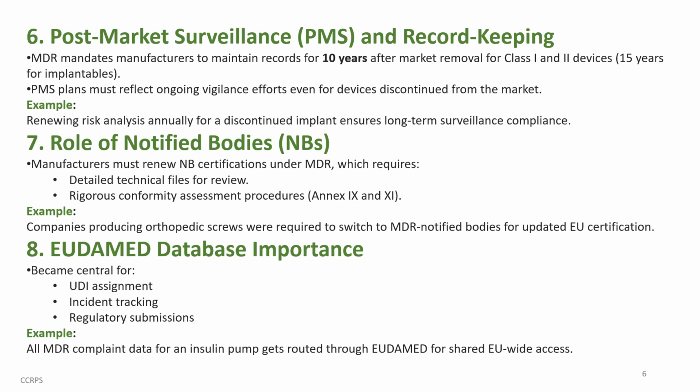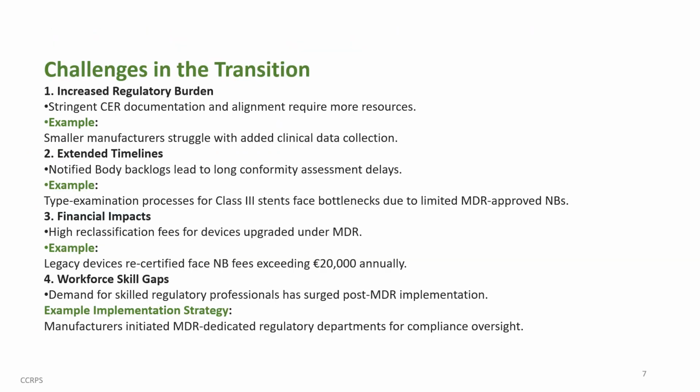Role of NBs, or notified bodies. Manufacturers must renew NB certifications under MDR, which requires detailed technical files for review. Rigorous conformity assessment procedures, Annexes 9 and 11. Example: companies producing orthopedic screws were required to switch to MDR notified bodies for updated European Union certifications. EUDAMED data's importance: it became central for UDI assignment, incident tracking, and regulatory submissions. Example: all MDR complaint data for an insulin pump gets routed through EUDAMED for shared European Union-wide access.